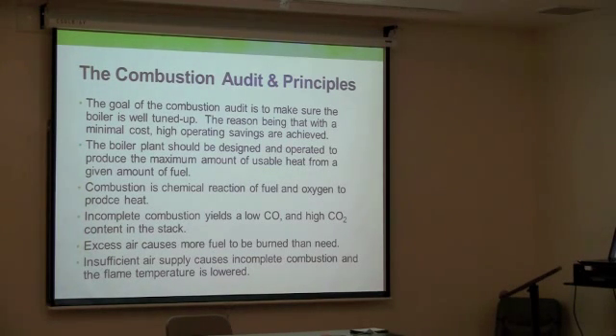So let's make it conservative, and let's pass 12 units of air instead of 10, so I make sure I have enough oxygen for combustion. Now what happens is, air is coming from outside. When you combust it, it gets hot, right? So now you're basically heating up 2 extra units of air for no reason, just because you wanted to be conservative.